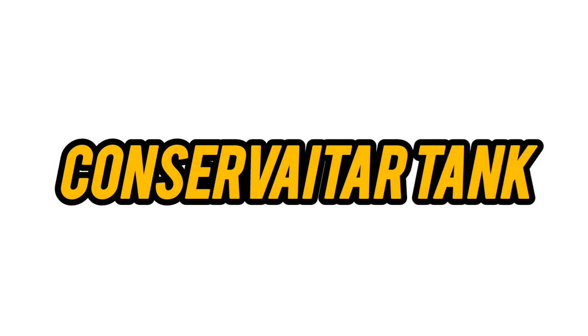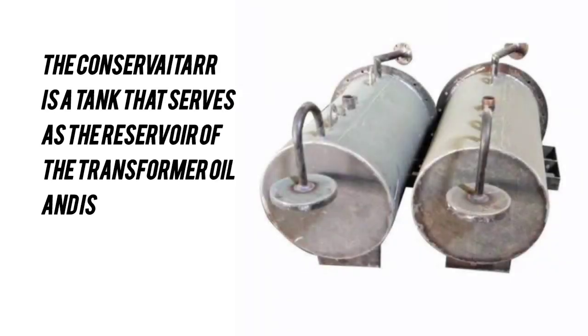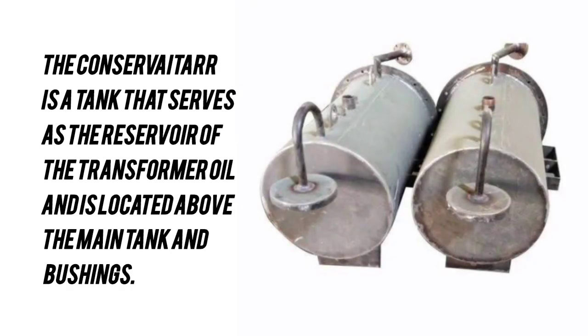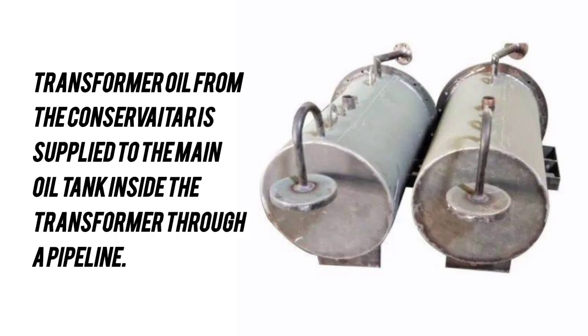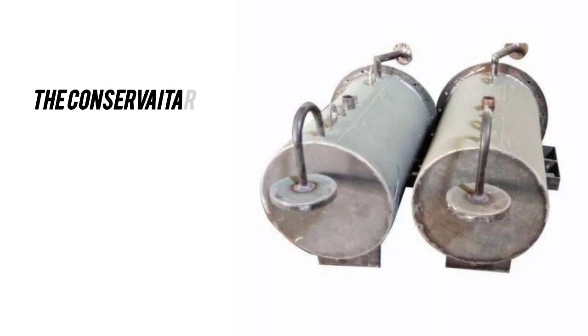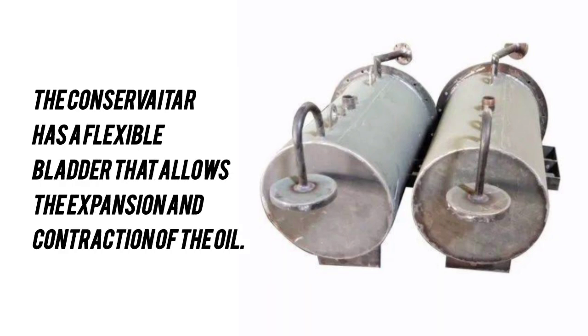Conservator tank. The conservator is a tank that serves as the reservoir of the transformer oil and is located above the main tank and bushings. Transformer oil from the conservator is supplied to the main oil tank inside the transformer through a pipeline. The conservator has a flexible bladder that allows the expansion and contraction of the oil.